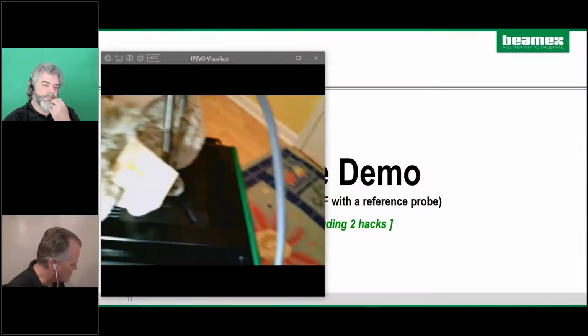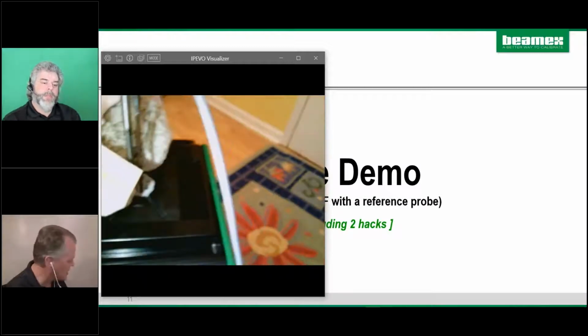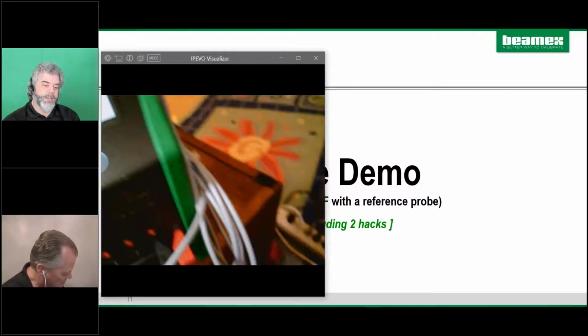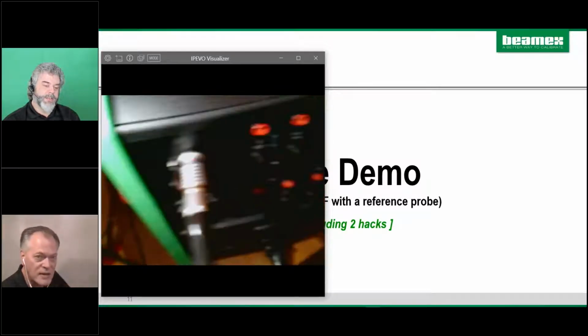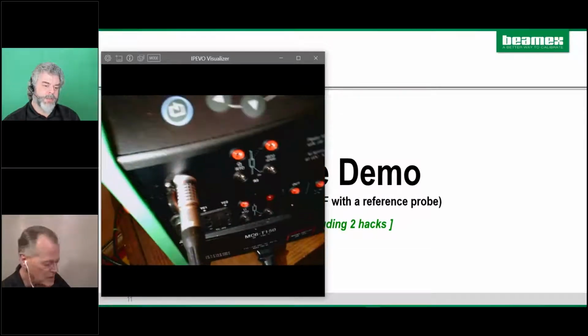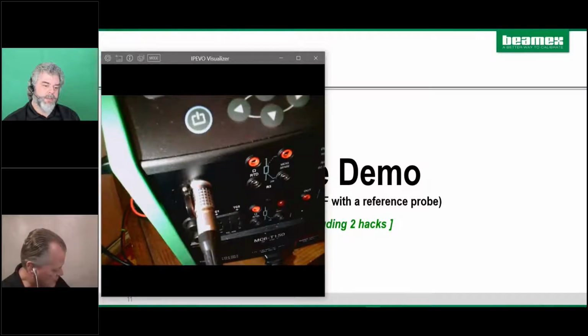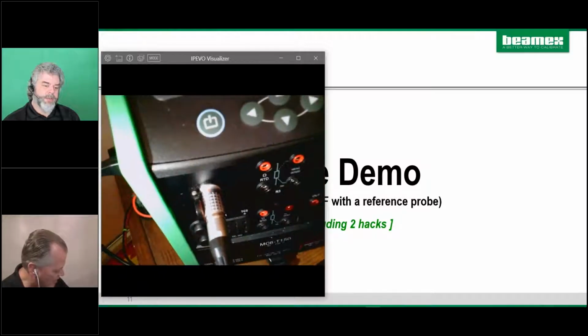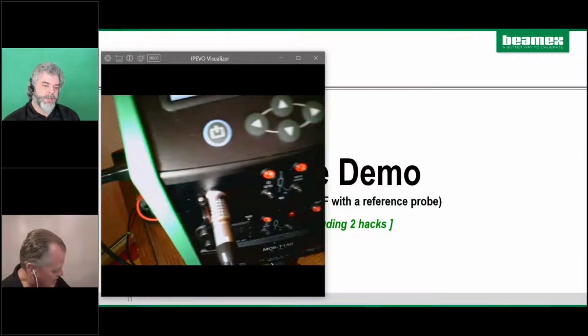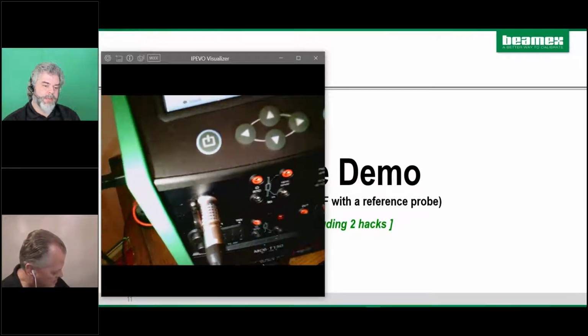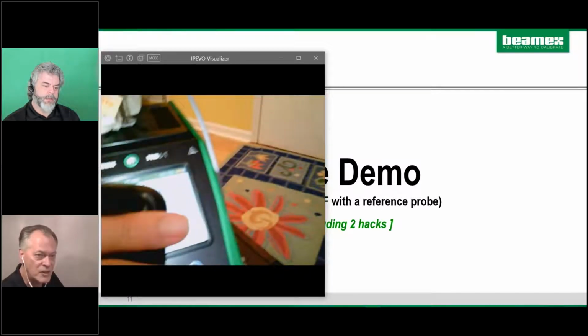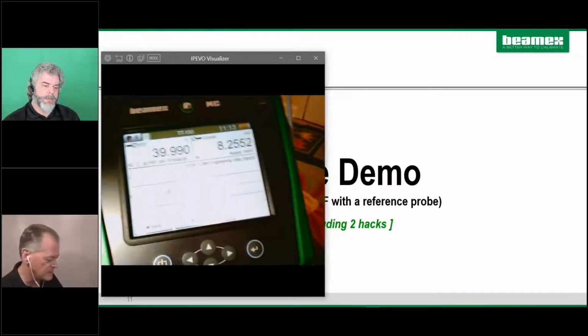And remember, I said we had a reference probe. So this skinnier probe gives us accuracy out to the second decimal. That cable is plugged in here at this LEMO junction. For this calibration, we're going to be comparing the LEMO connection measurement to the milliamps that you see on the screen here.